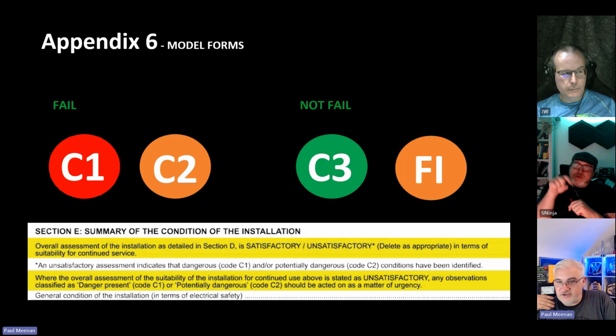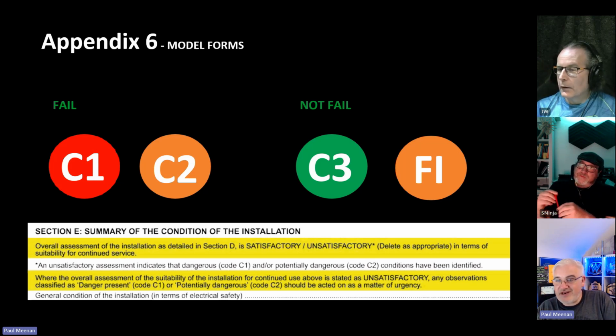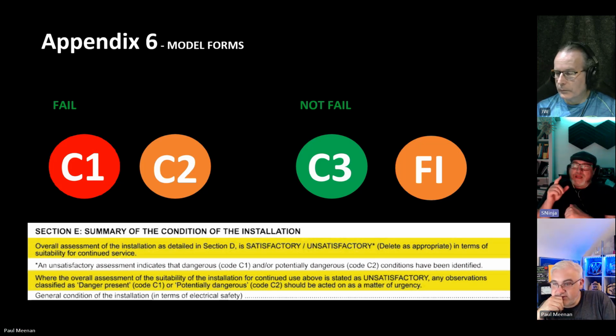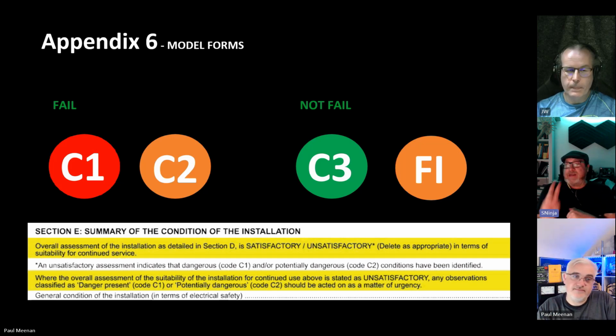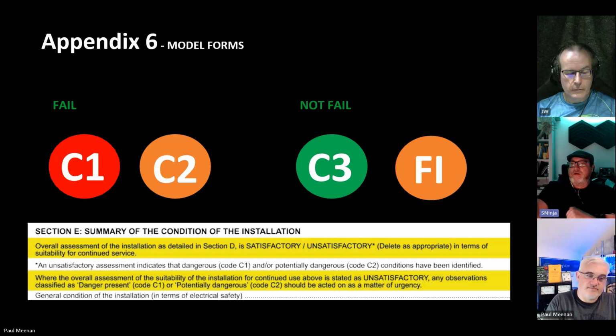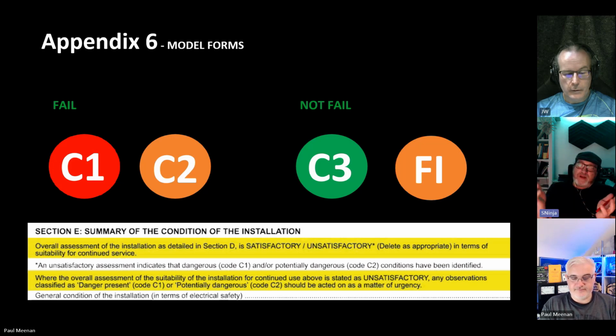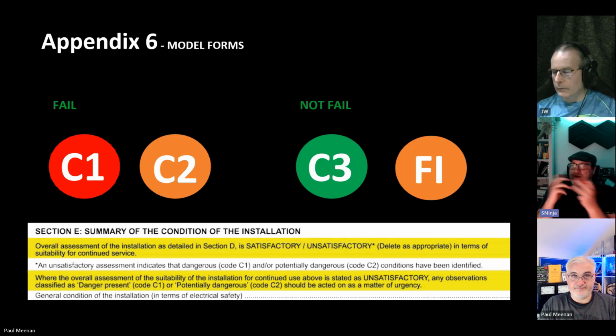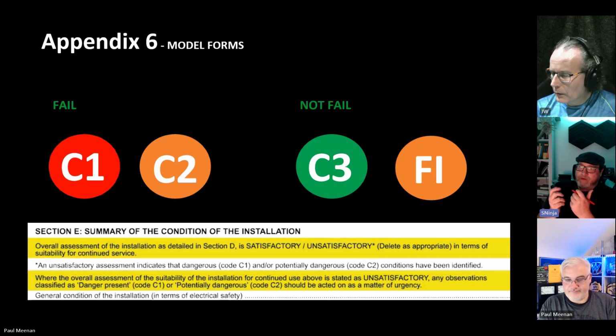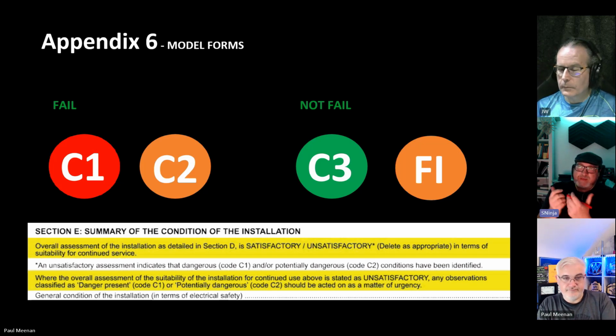When I was training, it was supplementary protection, and you would never ever code an RCD not being there as a failure of the installation. For me that's always down to the utilization behavior. If it's the same person using it the same way with the same equipment, there's no need for it. But if there's new people, more equipment, extension leads galore, this is why the inspector needs the freedom to actually make an inspection decision.